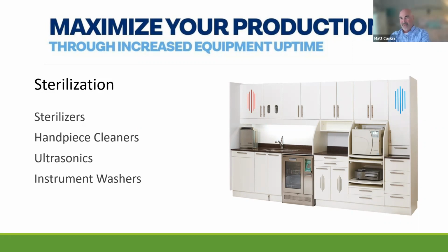Ultrasonics, pretty simple, right? You just want to make sure that you're changing out the solutions regularly, usually daily, sometimes more, depends what kind of cases you're doing. And as far as the cabinetry and all that kind of stuff, no harsh abrasives. You want to make sure you're using what the manufacturer recommends, and that's something I'll get into a little bit later with the operatories as well. But no harsh chemicals. Use the recommended cleaners. You want this stuff to last a long time, so just make sure that you're using the proper cleaners. Keep it looking nice and new.